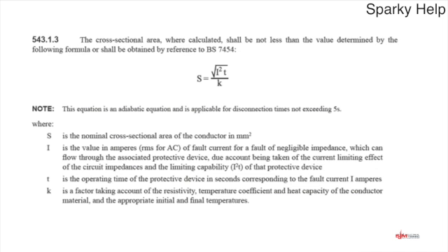543.1.3. The cross-sectional area, where calculated, shall not be less than the value determined by the following formula. This is the adiabatic formula, which gives reference to another British Standard. So S is equal to the square root of I squared times t, divided by k. Underneath it says this adiabatic equation is applied for disconnection times not exceeding 5 seconds. Also below that, it tells you what all those S, I, t and k all mean. And it's a long-winded calculation, but one I will cover.